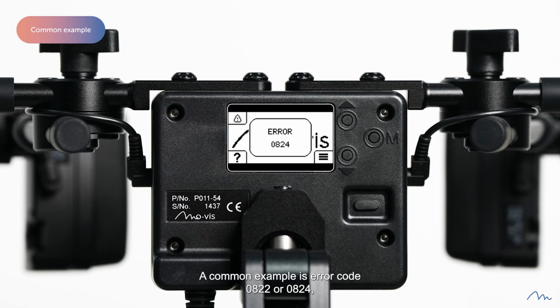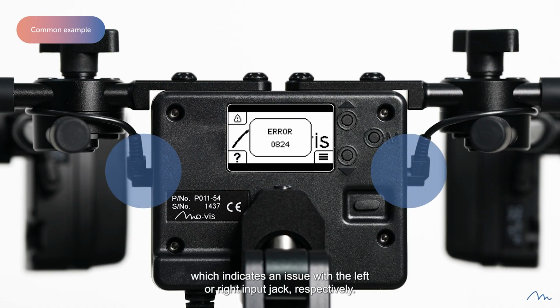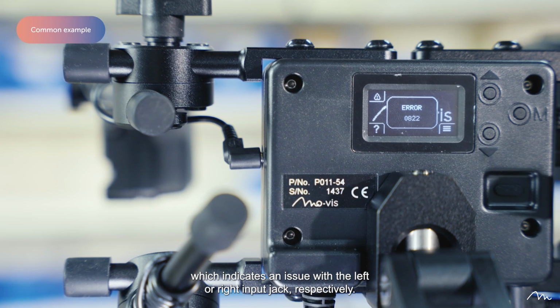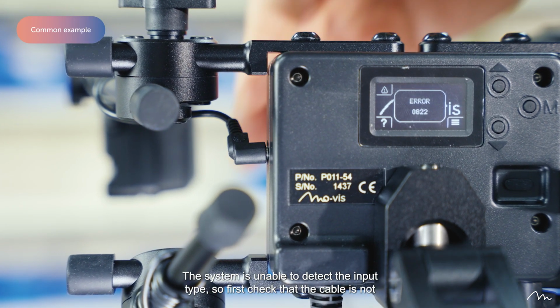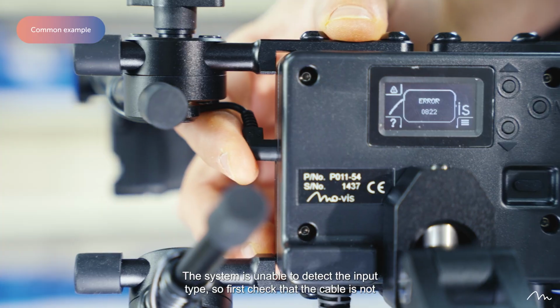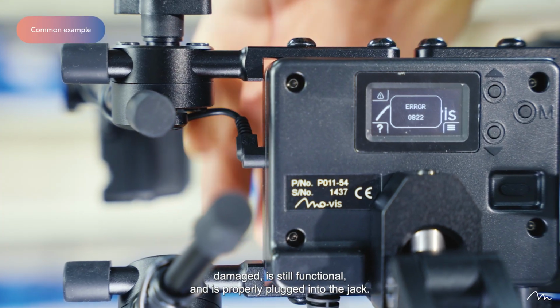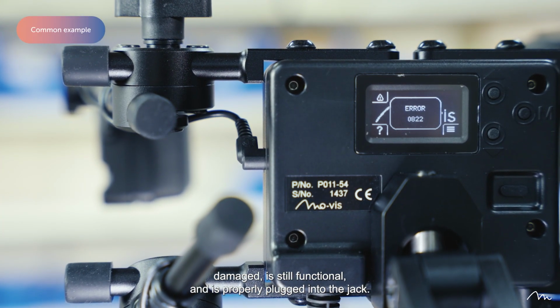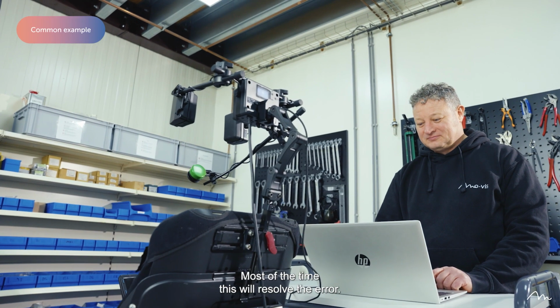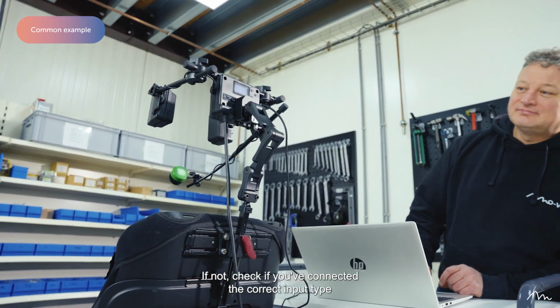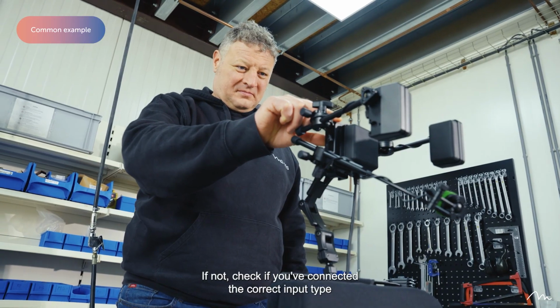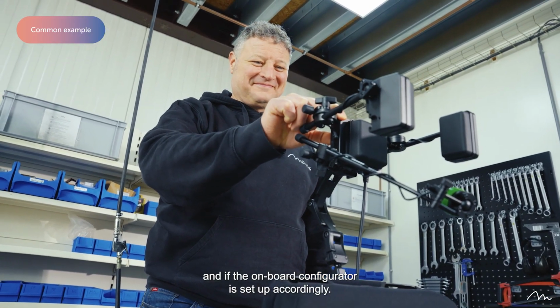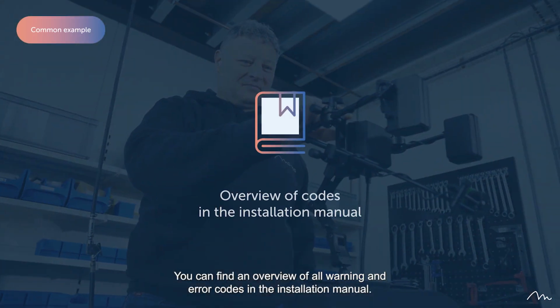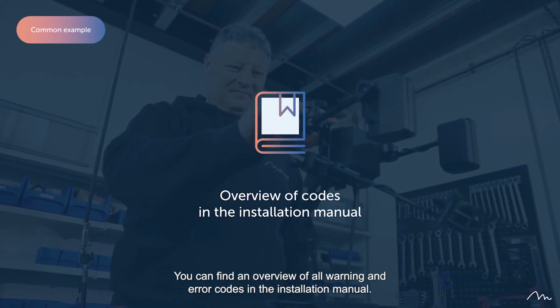A common example is error code 0822 or 0824, which indicates an issue with the left or right input jack, respectively. The system is unable to detect the input type, so first check that the cable is not damaged, is still functional, and is properly plugged into the jack. Most of the time, this will resolve the error. If not, check if you've connected the correct input type and if the onboard configurator is set up accordingly. You can find an overview of all warning and error codes in the installation manual.